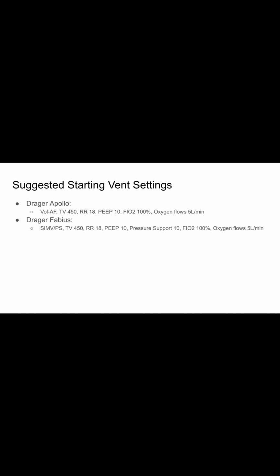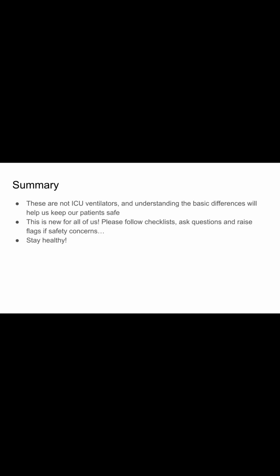If you are setting up a Draeger Fabius machine, we recommend the SIMV pressure support mode with tidal volumes of 450, again a respiratory rate of 18, a PEEP of 10, but make sure that you're setting pressure support to 10 centimeters of water, and then again 100% FiO2 and 5 liters of oxygen flow. So in summary, these are not ICU ventilators, but understanding basic differences I think will help us to keep our patients safe and anticipate problems before they happen.